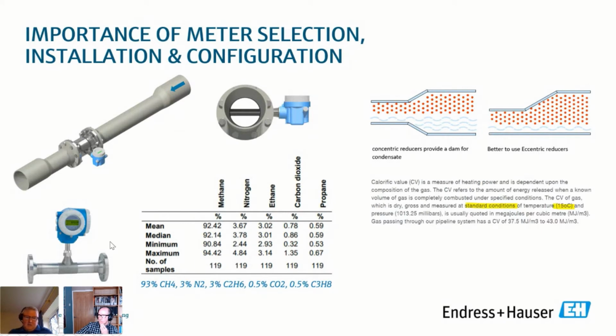Now, the key thing about the measurement of gas is that it should be corrected. The volumes that we're getting need to be corrected to standard conditions. This is a caption again from the National Grid website, and it's just to highlight that the CV of gas is the amount of megajoules, the amount of energy you've got in a cubic meter, but that cubic meter is referenced to standard conditions. So standard conditions are 15 degrees C and 1.013 bar absolute. If we're going to get fuel and convert it to kilowatt hours, we have to have the right units. You can't just have volume that's corrected to 0 degrees and multiply it by the calorific value that's corrected to 15 degrees. You'll get a 5% error in the energy. So attention to detail has to be made to get the units corrected to 15 degrees C.